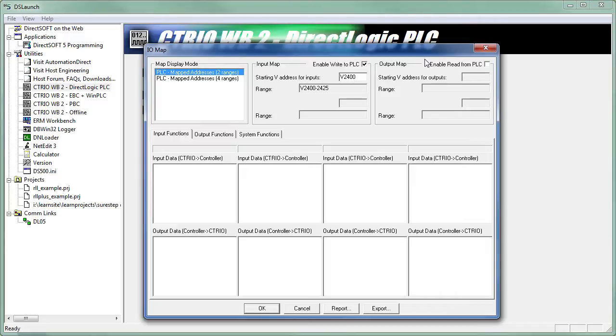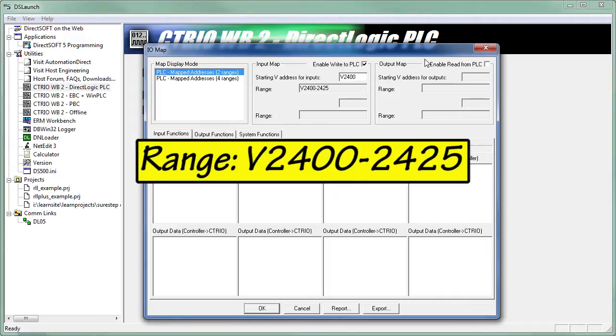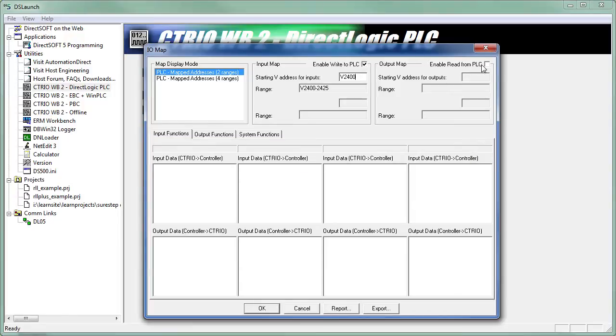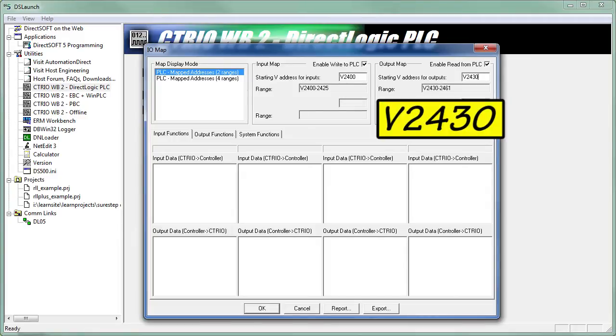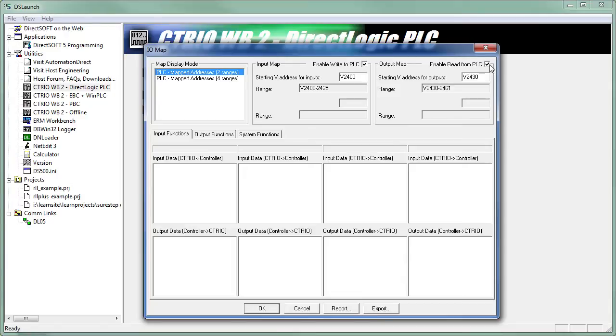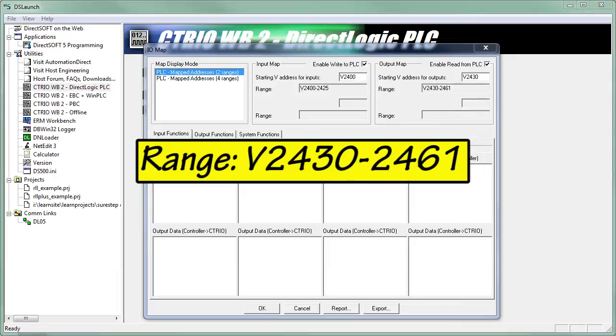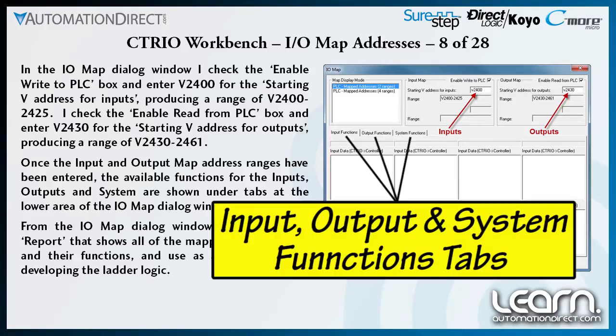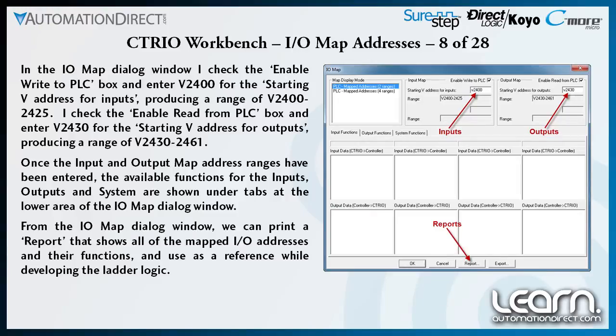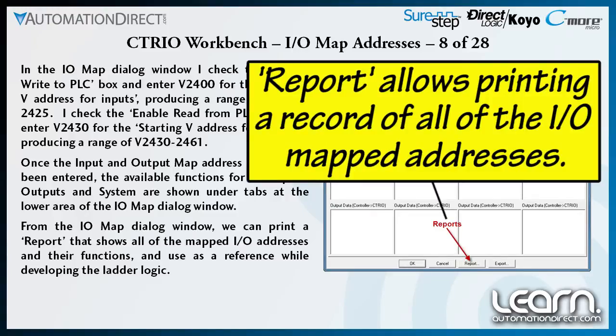This produces a range of memory registers from V2400 to V2425. Next, I check the Enable Read from PLC box and enter Memory Register V2430 for the starting V address for outputs, which gives me a range of memory registers from V2430 to V2461. The available input, output and system functions will now be shown under the respective tabs. A report showing all of the mapped I/O addresses and their functions can now be printed from this dialog window and used as a reference for developing the ladder logic.